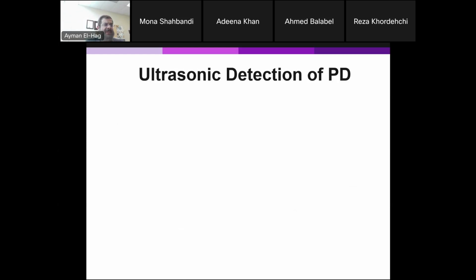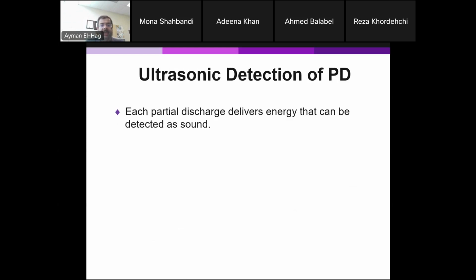Finally, the ultrasonic. We mentioned there are also ultrasonic waves produced. Every discharge comes with a sound. Now, there are sensors called acoustic emission sensors. It could be in the audible region, not the ultrasonic, but the regular region. Some sensors do that. But to measure a discharge from 20 hertz to 20 kilohertz, the range of frequencies that we can hear, it has to be very intense. But from our experience, when you use an ultrasonic sensor, above 20 kilohertz, even if you can't hear anything, the partial discharge could be small in quantity, but it produces discharges in that range of frequencies, and the sensor can efficiently detect it.